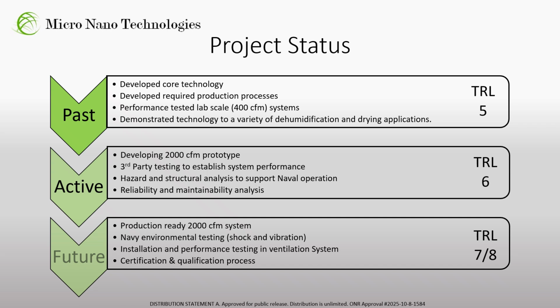MNT has developed the core technologies used in this system, experimentally tested them in a lab setting across a wide range of inlet air dew point conditions, and developed a set of validated simulation models to support the system's scale-up and design. These validated models were used in our Phase 1 effort to establish the feasibility of this system to meet the Navy ventilation air requirements. Additionally, MNT has developed and proven a set of production processes enabling low-rate production.